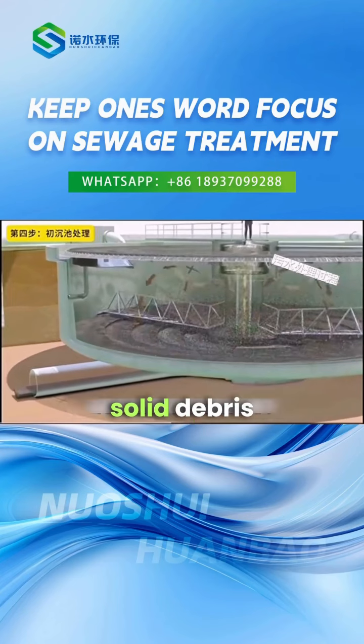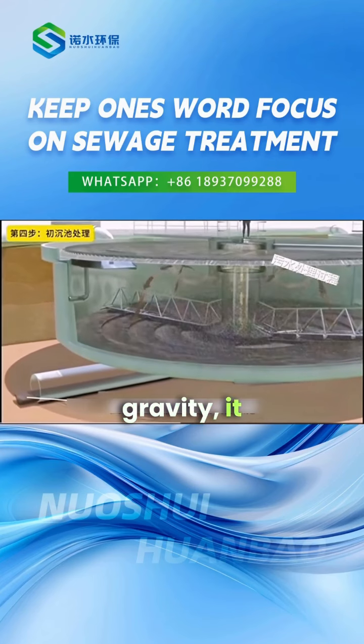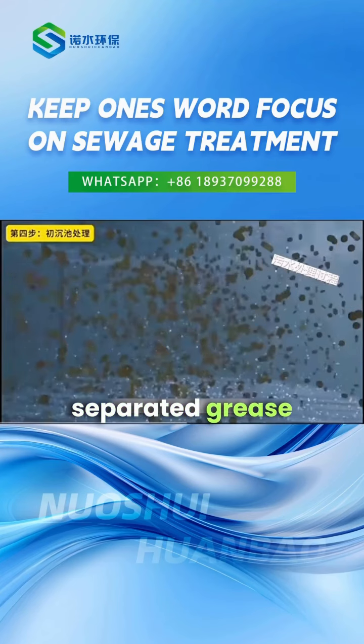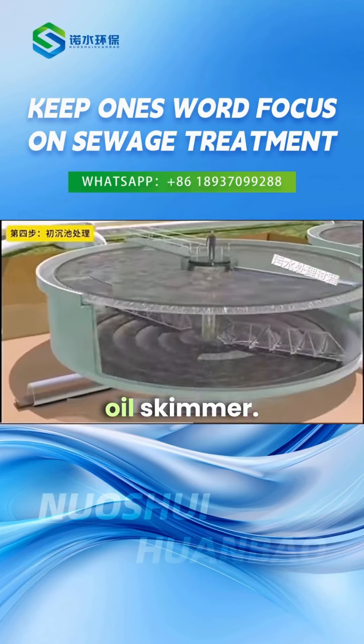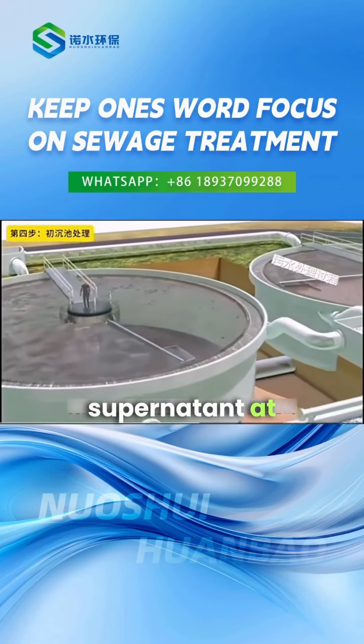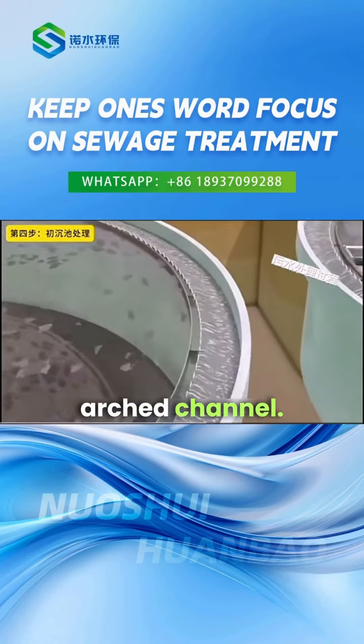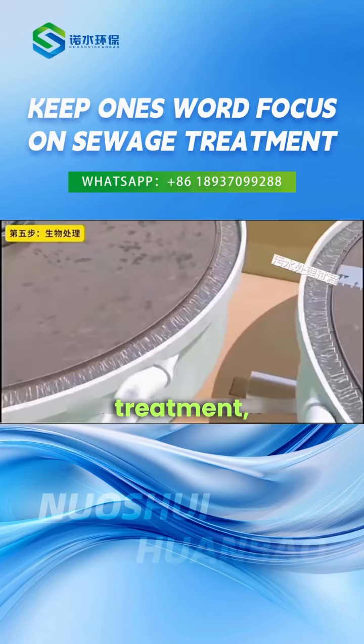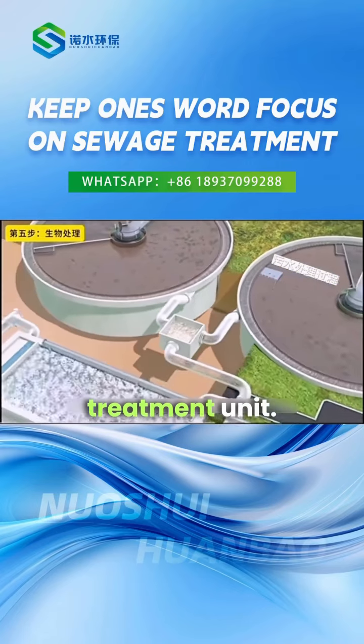When suspended solid debris settles to the bottom under gravity, it forms sludge, while the separated grease at the top is removed by an oil skimmer. Additionally, the supernatant at the top is discharged through an arched channel. After this preliminary treatment, the water will enter the biological treatment unit.